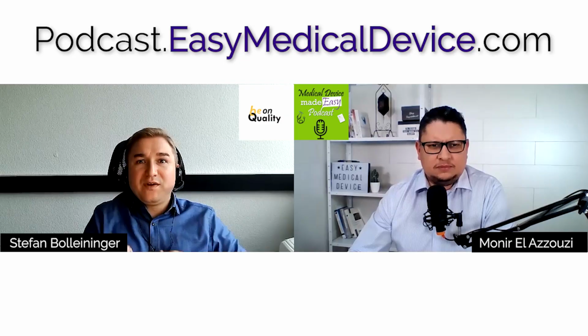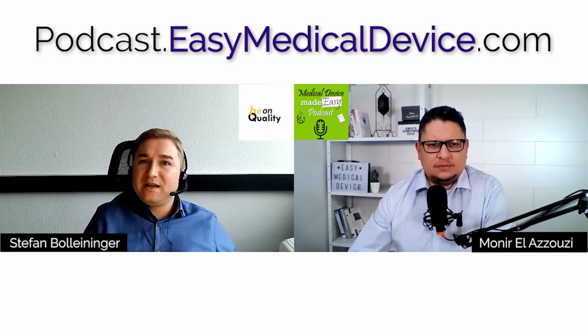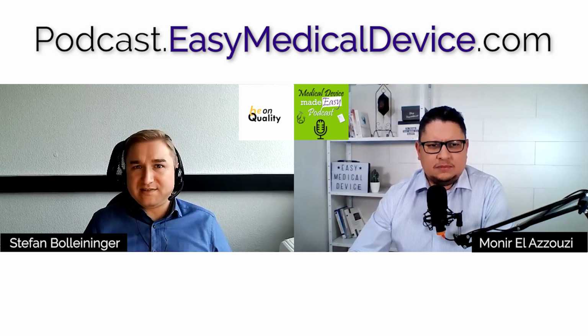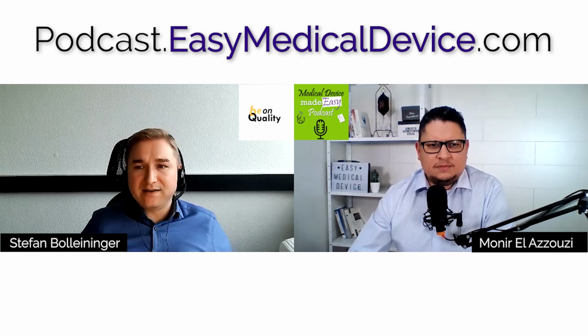And that's for the Annex 16 devices. You have safety, as you said, Munir, it's a safety you have to fulfill, and it's performance, which can be done by technical, by bench, or all of that. It's no real clinical use case, so no clinical evaluation. Okay. But it's important to do that, and this is not in the common specification right now.